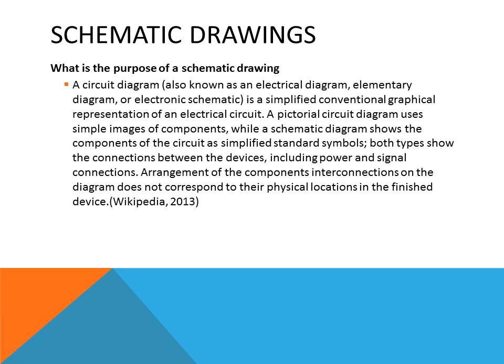And because of this, the schematic type diagram is sometimes called a ladder diagram, because the branch lines are usually stacked on top of each other like the rungs on a ladder. And so it makes it very easy to find out what's controlling the loads in each branch line. So for troubleshooting, this is the best tool to understand how a system is operating and electrically sequenced.